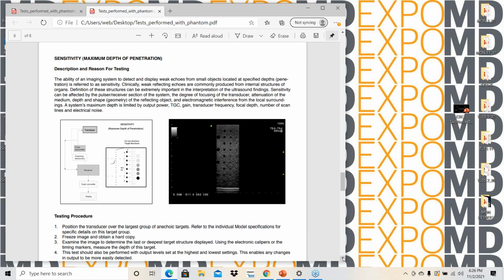And you say, well, why do I have to test? We're looking for penetration. Why wouldn't we just use a penetration setting? Because when you're using a penetration setting, what do you lose? Resolution, exactly. And when you do that, you may not see that tiny object that you're looking for, even though you're set up to go deeper. You have to have a larger object to be able to see it. So you'll see it at a deeper one if it's a large object.